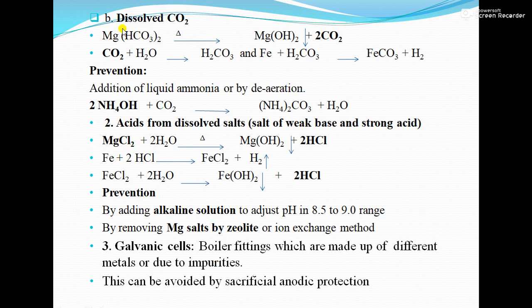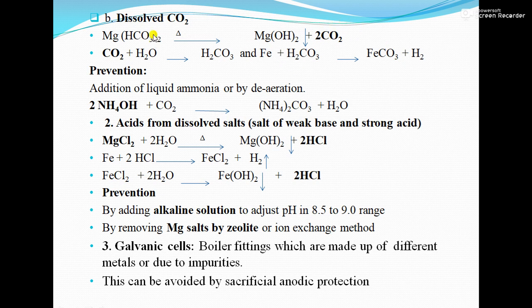Second is dissolved CO₂. Carbon dioxide is generated in water when water is heated and contains temporary hardness like magnesium bicarbonate, which converts into magnesium hydroxide precipitate and two molecules of CO₂. Also, during the journey of water from clouds to the earth, gases like CO₂ and SO₂ get mixed in. CO₂ reacts with water to form carbonic acid, which reacts with the iron boiler metal to produce ferrous carbonate.